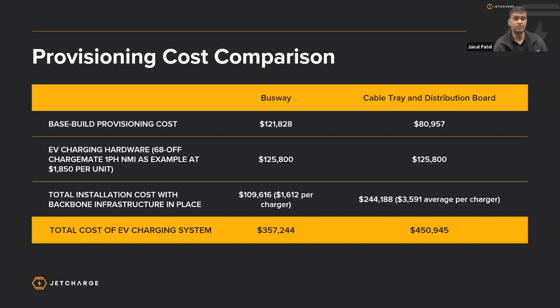But because we're running much shorter cable runs, we essentially have a cheaper installation cost once all the backbone infrastructure is placed in. So at the end of our EV charging installation, once everyone has taken up an EV, we've allowed for a $357,000 budget for the busway solution, but that number goes up by 100,000 for the cable tray distribution board method, which is our more traditional method. The busway is a better outcome for the client, as well as for the electricians who have to install the chargers after the fact, because they do not have to run the cabling back to a distribution board, which saves a lot of cost. And that's it in terms of the design considerations that we take for EV charging.